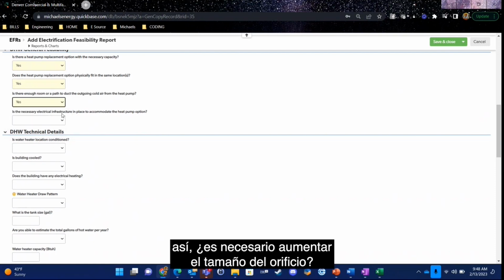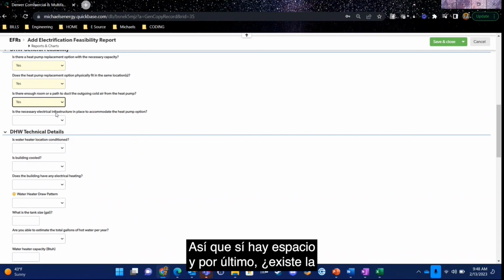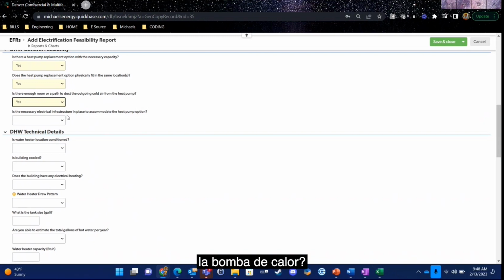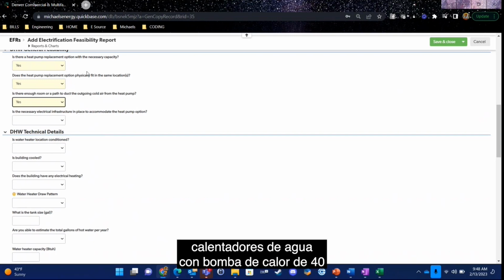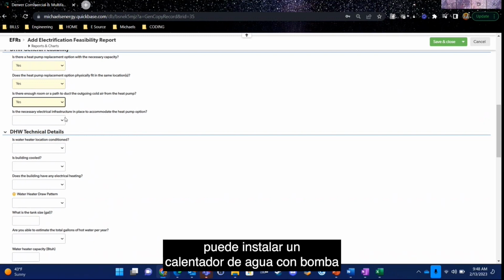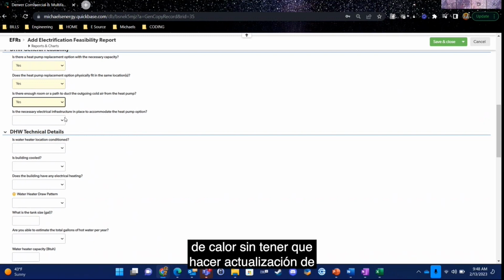Is there the necessary electric infrastructure in place to accommodate the heat pump? If you don't know offhand, do some research. There are 40-gallon heat pump hot water heaters now. I think Rheem makes a brand that's 120 volt, so even with a standard 120 volt outlet, in many cases you can install a heat pump hot water heater without an electric infrastructure upgrade or capacity increase. But that depends on the unit you're speccing. So in this case, I'm going to say yes.